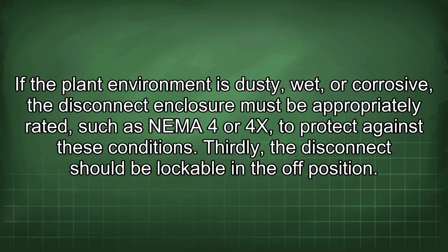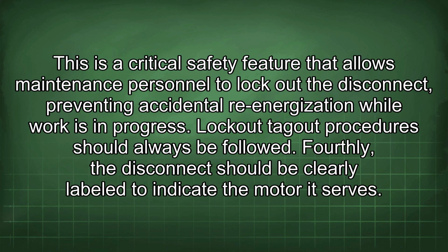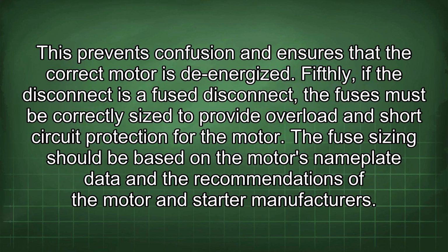Thirdly, the disconnect should be lockable in the off position. This is a critical safety feature that allows maintenance personnel to lock out the disconnect, preventing accidental re-energization while work is in progress. Lockout-tagout procedures should always be followed. Fourthly, the disconnect should be clearly labeled to indicate the motor it serves. This prevents confusion and ensures that the correct motor is de-energized.